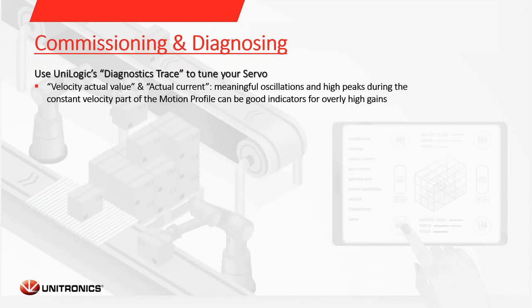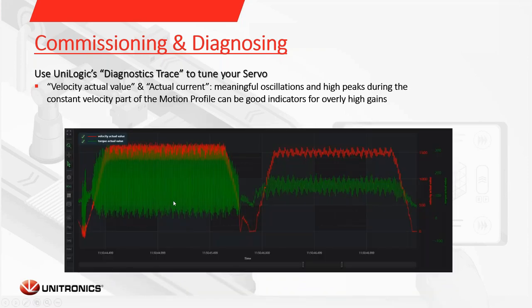You can use our diagnostics trace to tune your servo. I recommend recording the velocity actual value and the actual current value. The way to tune it is pretty easy: if you see meaningful oscillations or high peaks during the constant velocity part of the motion profile, that indicates gains are too high. On the left, you can see the green torque actual value jittering a lot and reaching relatively high values. On the right, you can see the trapezoidal velocity motion profile with the current at a relatively constant value during the constant velocity phase.